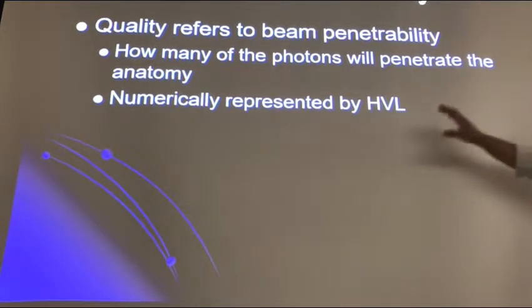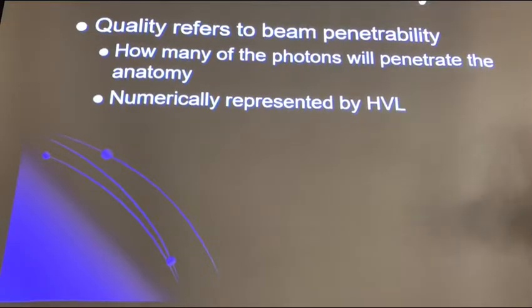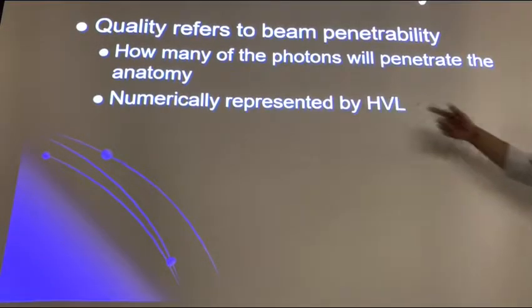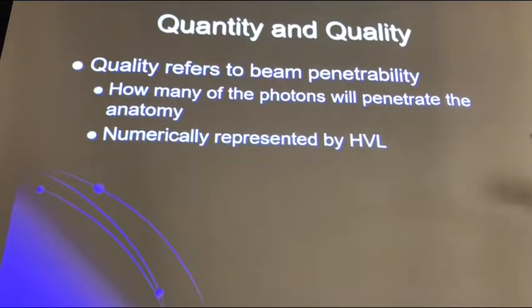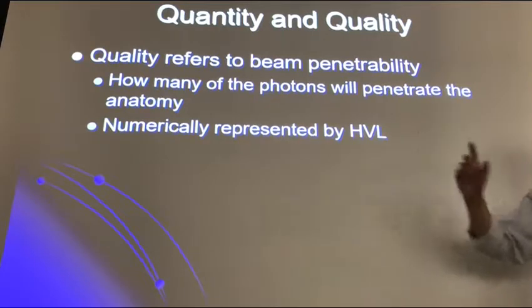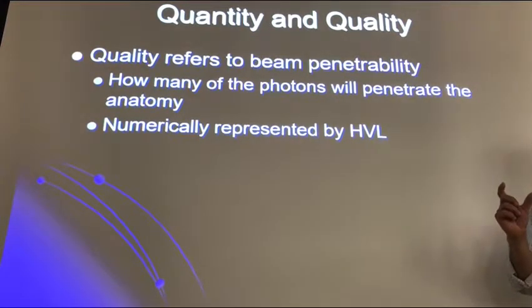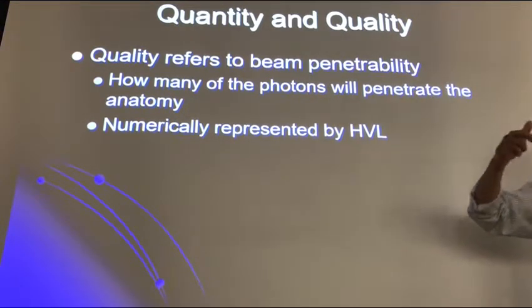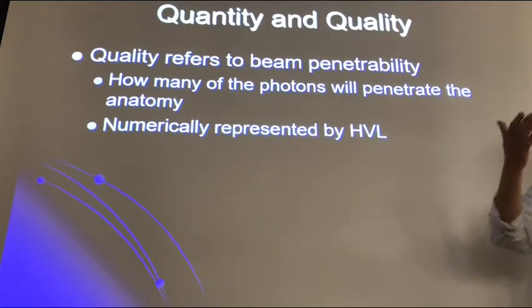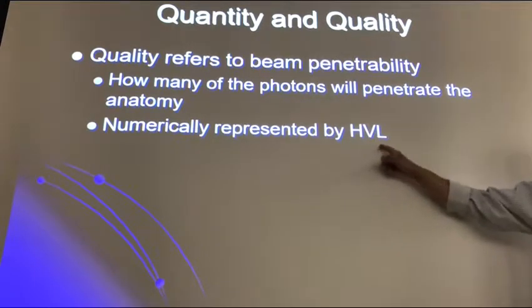The half value layer is important. When you're measuring penetrability, you cannot measure it just by KVP — KVP is a factor that influences penetrability. But the way to measure it is with the half value layer.